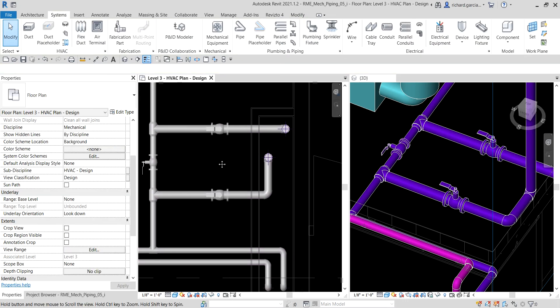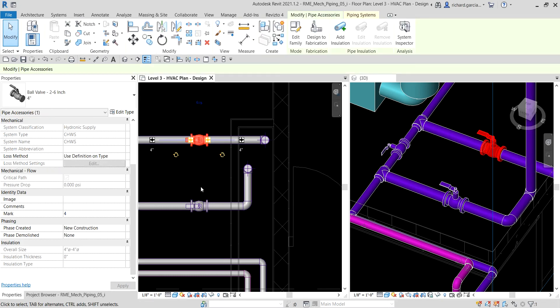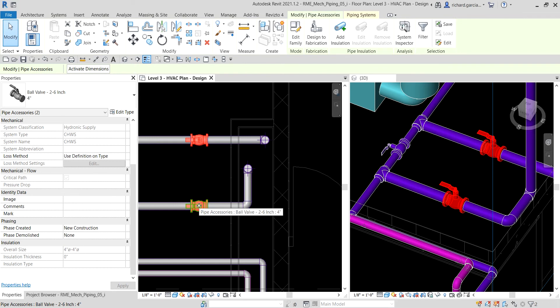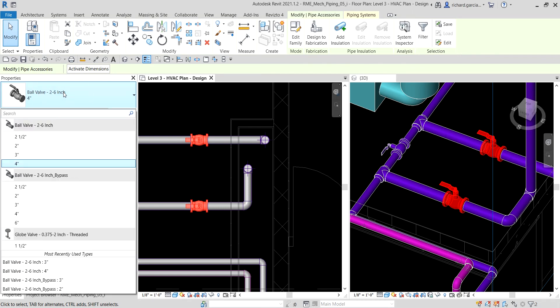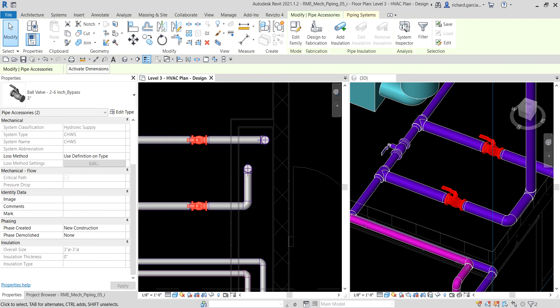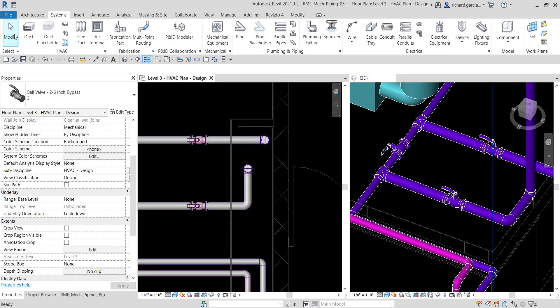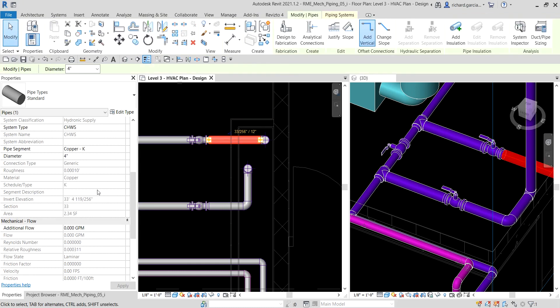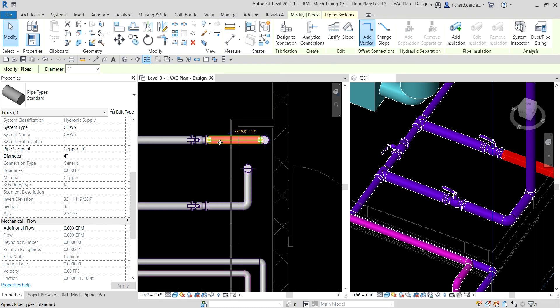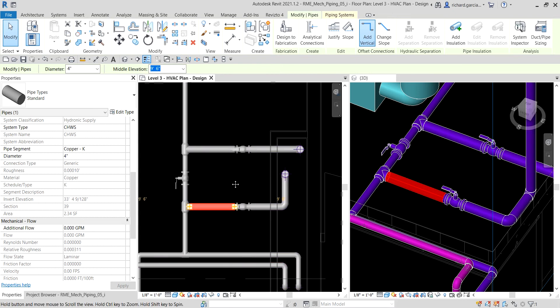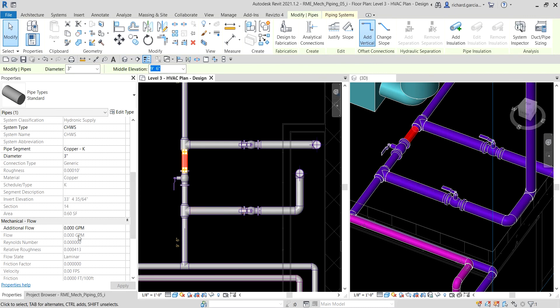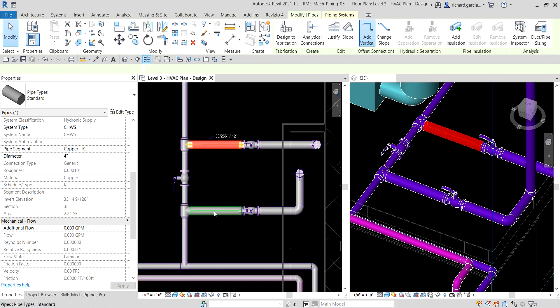Then I'm going to select the two regular ball valves — click and hold Control and then click that one. We're going to change those to bypass valves, using three inches. You will now notice that the flow becomes zero here. Same with this return pipe to the cooling tower — it becomes zero. For this one, it's also zero. So because we modified our valves there.